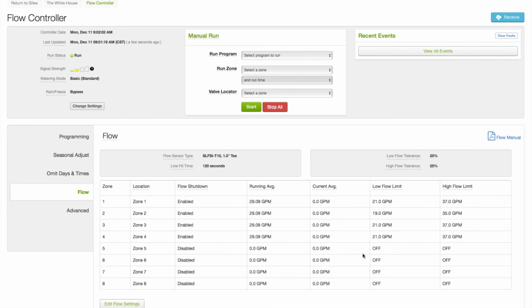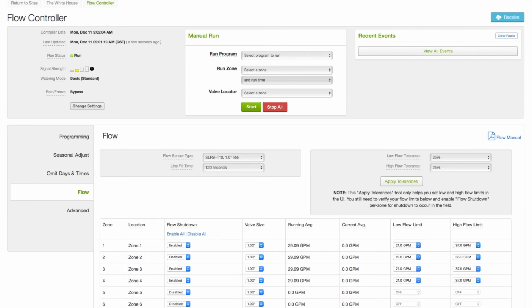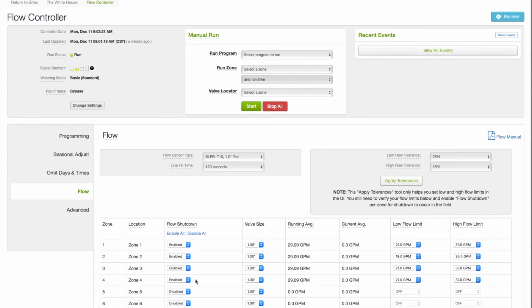So again, a couple of things to keep in mind. Just to reiterate, if I enable the zone flow alert, I also have to change the threshold, and if I change the threshold, I also have to enable the flow alert, or else when it comes back on the overnight, these will be disabled and this will go back to 0. So I have to do both of these simultaneously.